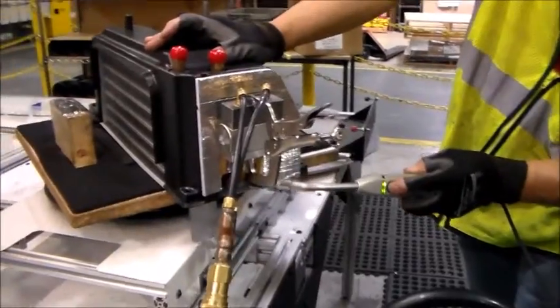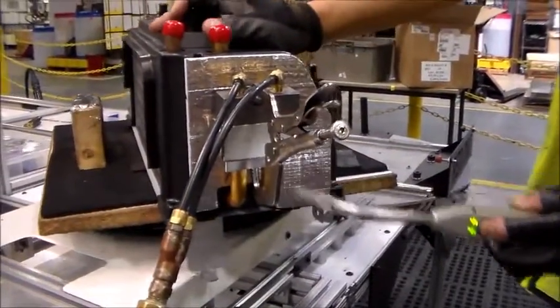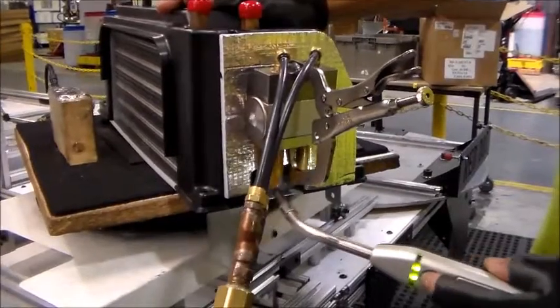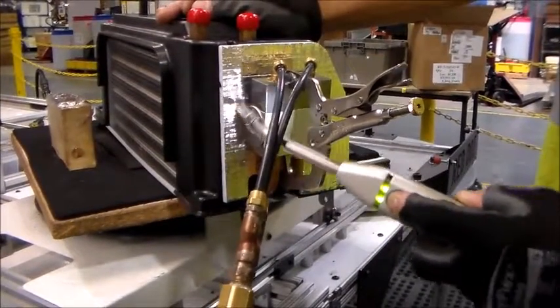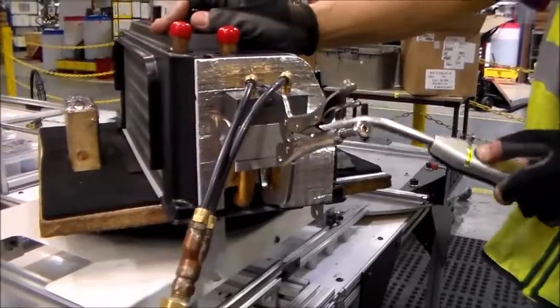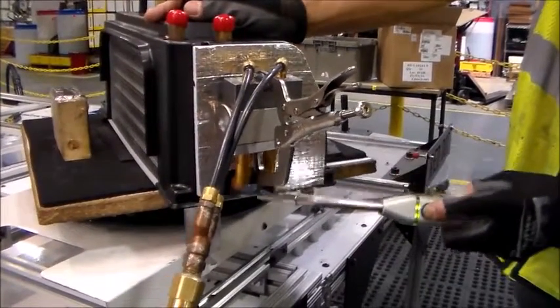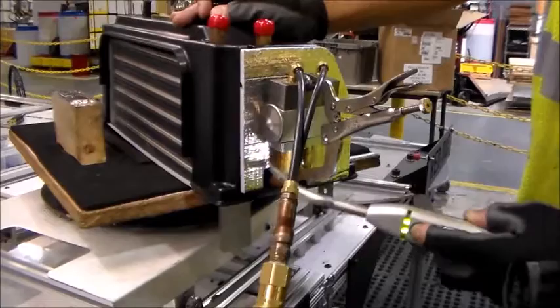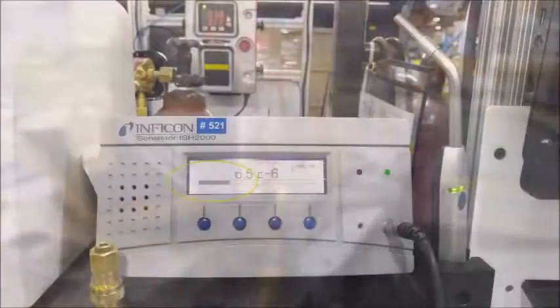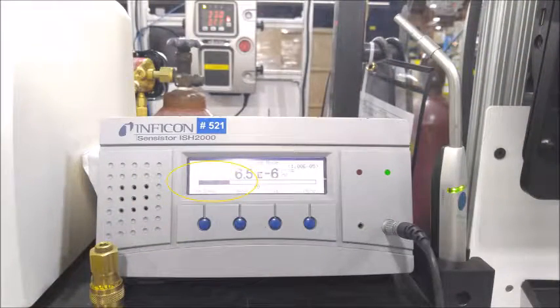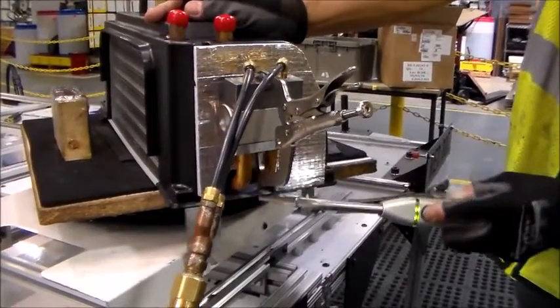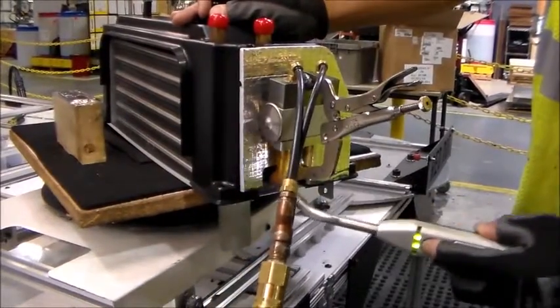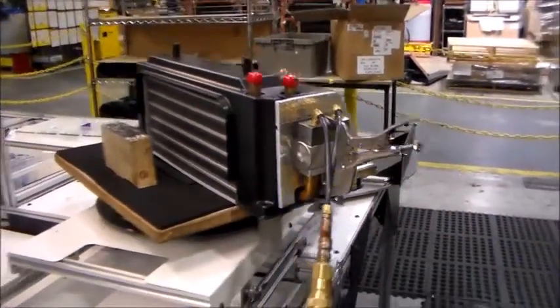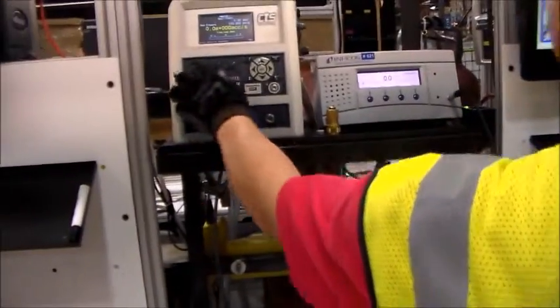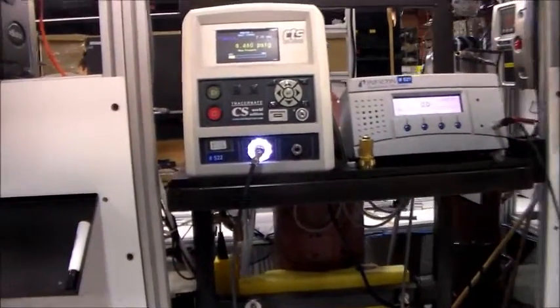Take the test probe for the ISH 2000 and place it in contact with the joint specified on the method sheet. Hold the probe in place for at least 2 seconds and slowly move the probe around the joints. Pay special attention to the joints around the expansion valve and their O-rings, any gasket seals, or other joints shown by the method sheet. You'll see the detection bar on the ISH 2000 move if any leak is present. If the probe doesn't detect a leak, the bar on the ISH 2000 will remain at 0 and the part contains no leaks. Press Start again to complete the test and evacuate the part of any remaining tracer gas.